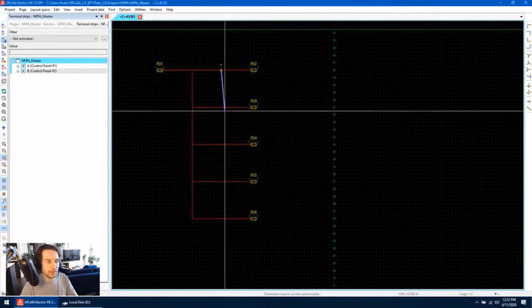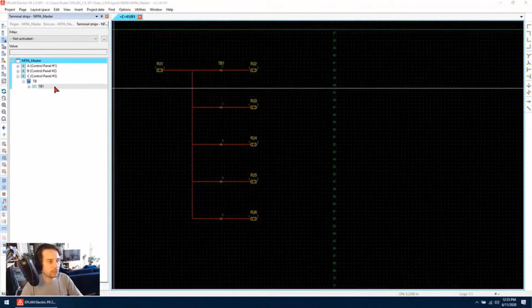Once we've done that, Eplan will work out that we need saddle jumpers between all of the terminals since we have connections running between them. We can see this by going to the terminal strip navigator and right-clicking on the terminal strip and going to Edit. Here we can see that Eplan has automatically generated these saddle jumpers for us.